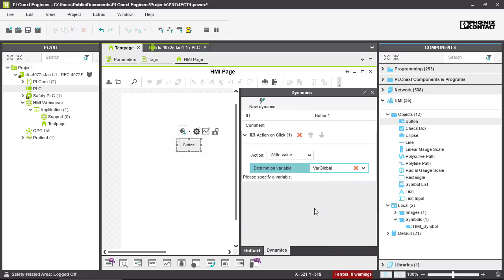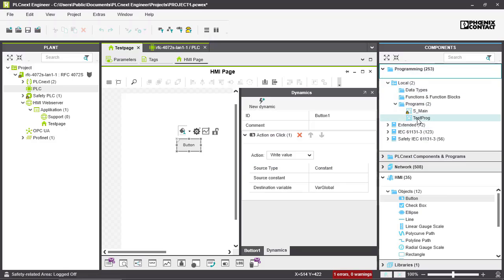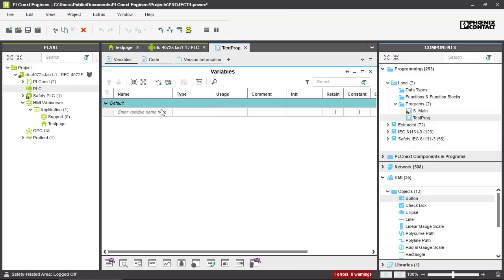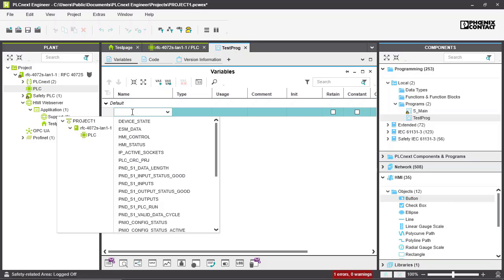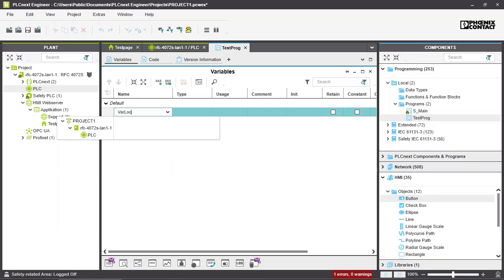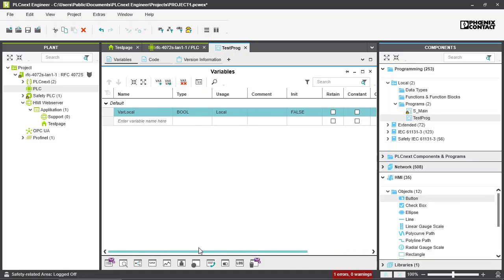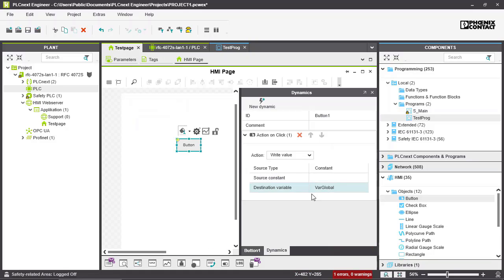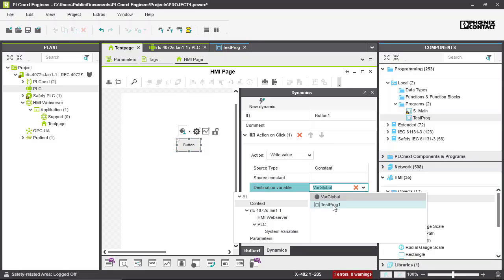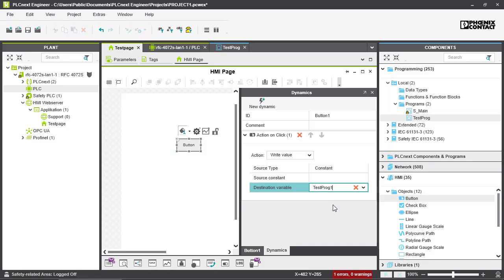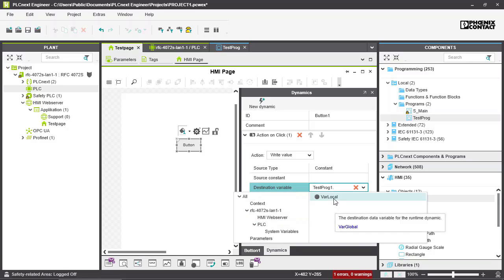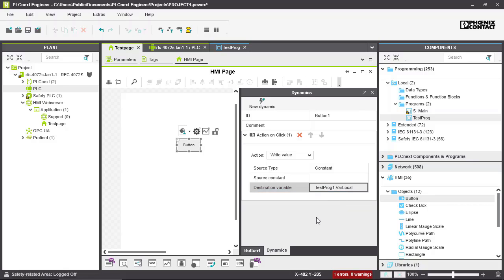We can also use local variables — for example, in a program. Go into the variable list of the program and enter a name for the variable, such as 'var_local'. Importantly, you need to activate the HMI usage flag. Then go back to the test page, select the test program, and select the variable by adding a dot and choosing 'var_local'. That's how you create a button linked to a variable in your HMI page.